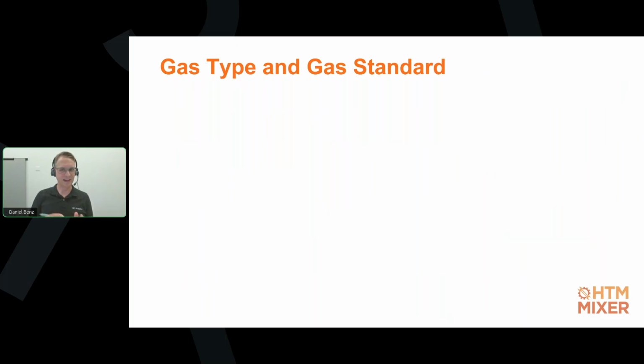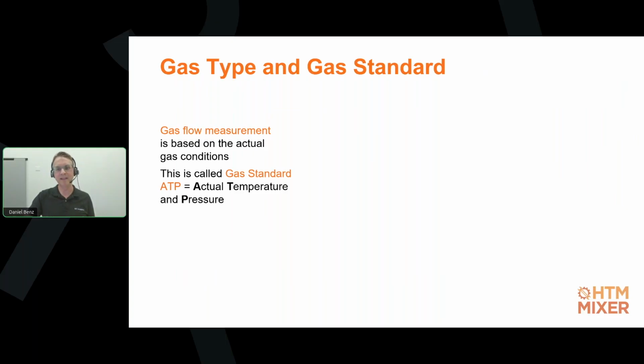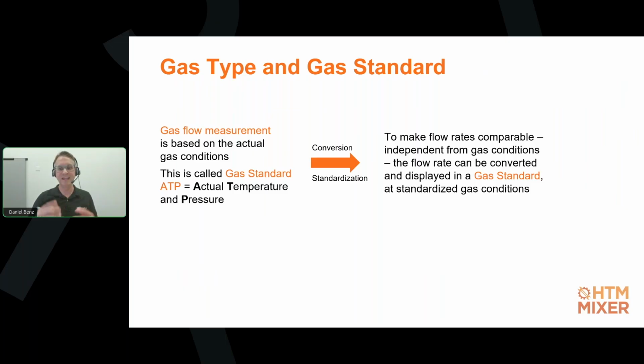In order to understand the meaning of a gas standard, we first need to understand the separation between gas flow measurement and gas flow displaying. As we have seen in the previous slide, the gas flow measurement is based on the actual gas conditions. This is typically called the gas standard ATP, which stands for actual temperature and pressure. But in order to make flow rates comparable and independent from our gas conditions, the flow rate can be converted by the gas flow analyzer, and the result can be displayed in a different gas standard at standardized gas conditions. For example, how much flow would that be if the gas was 98 degrees Fahrenheit and 100% humid, even if it's actually not when we measure it with the analyzer. This conversion, or the value that we display, is considered gas flow displaying. So this is really something we have to separate: what we measure and what we display.